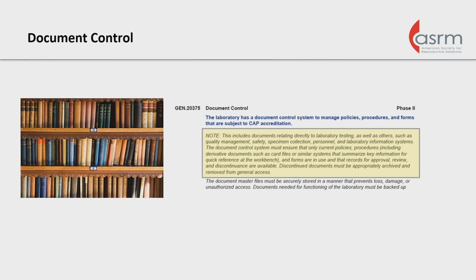CAP is moving toward a more ISO 9001-oriented type of questions related to quality management. A quality management system is a set of policies, processes, procedures, and resources designed to ensure high quality of an organization's services — this is your structure, your basement, the foundation you want to build everything else on. One of the most critical things in a laboratory is documents — controlling those documents and making sure they are the most up-to-date procedures. When inspecting laboratories, I constantly see procedures where people have written things in, sometimes initialing them or dating them, sometimes not. You need to control these documents.